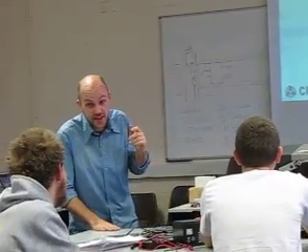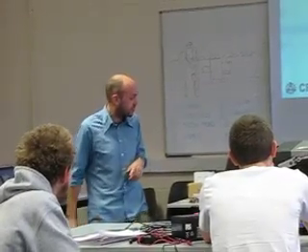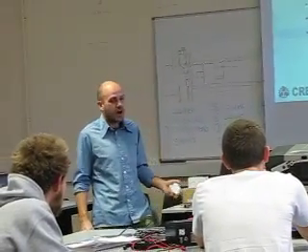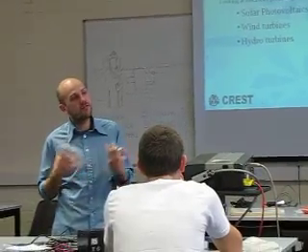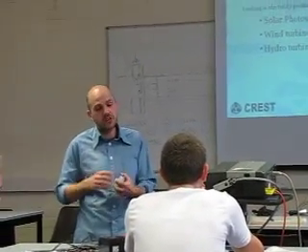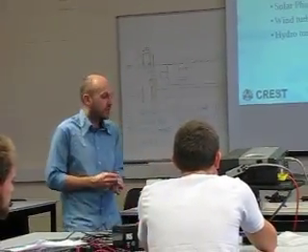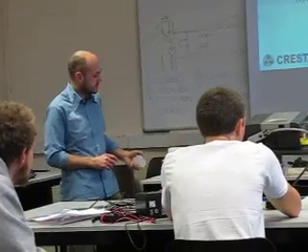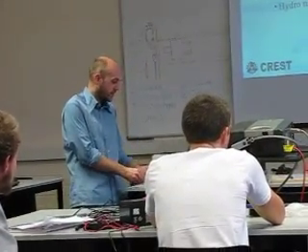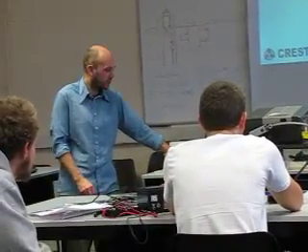Sorry? Charging. Yes, that's true. When they're charged, they give off hydrogen. Not these particular ones because these are sealed, but open vented ones give off hydrogen gas, which is flammable. If you don't vent it away correctly, there is the potential for a build-up of hydrogen gas and an explosion, especially if you have a spark. So that can happen. I'll come on to how you protect a battery in a bit and how we stop all these things.